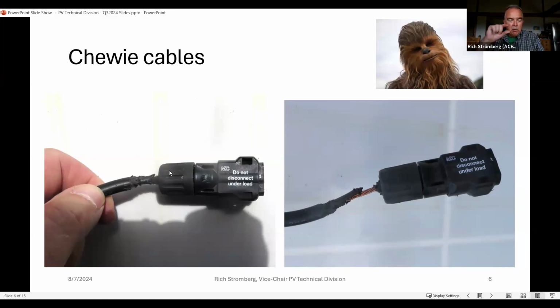But let's say you go from your original cable insulation and you've reduced that by 50%, whatever that thickness is. Well, you've reduced your voltage protection by at least that. And if this was designed for a 1,000-volt array and now you've lost some of that margin, you could still get arcing depending on exactly where there's other conductors here.